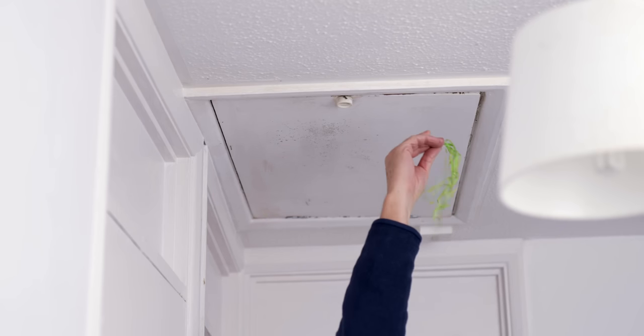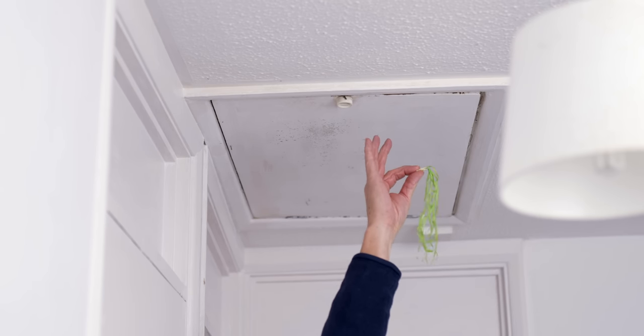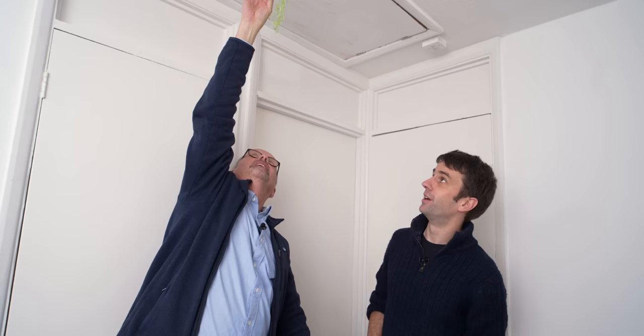The loft hatch is one of the key areas where a lot of air leaks out. With the fan running, we can see if we've got any air leaking through this one — I'm very confident we have. We can already feel it actually. That side of my head is colder already. That's amazing. So you've given me this very high-tech piece of equipment — look at that. You see that? That is blowing about. Incredible, isn't it? That is amazing. Because you would not think that if you just walked up.